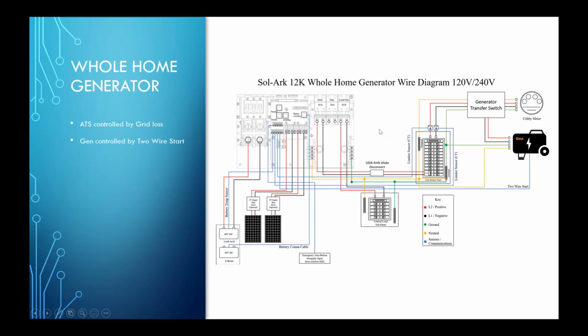So this is a larger generator, and it also has, as you can see, a bypass transfer switch right here in the design as well. And I'll let Dustin, you may want to go over this for us real briefly. Absolutely. So this does go over a very generic whole home kind of backup situation. Obviously, if a customer is looking at adding solar and they already have a whole home transfer switch, there's no reason to remove that transfer switch, as we can leave it where it's at, and then we can take advantage of it in the Sol-Ark whenever the grid fails. So in this case, we still have the gen breaker open, so you can actually turn that into a smart load, AC coupling, or really just use it for different kinds of points of connection.